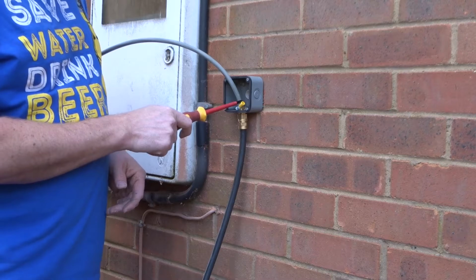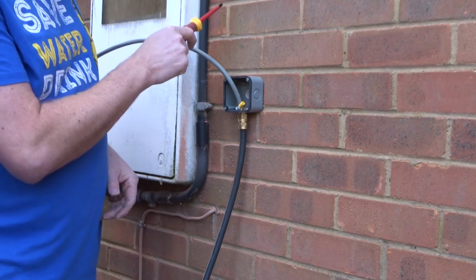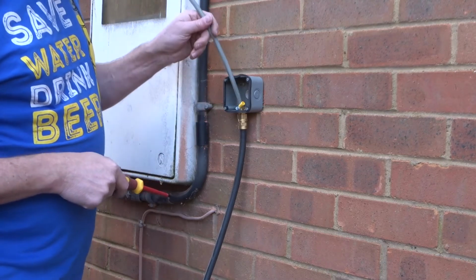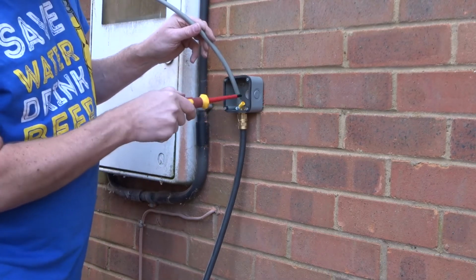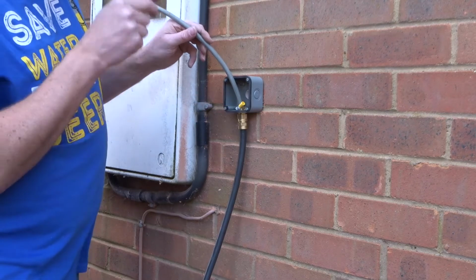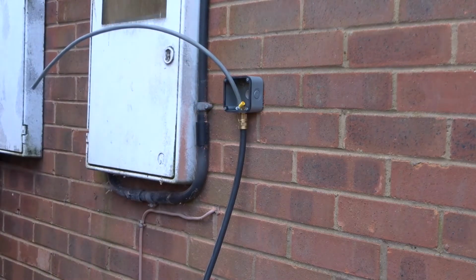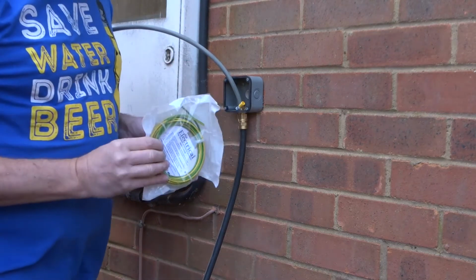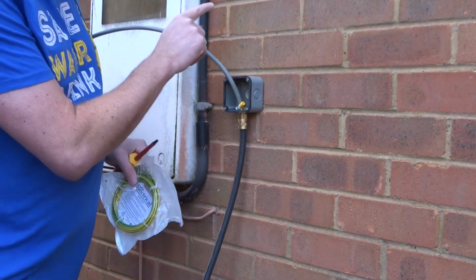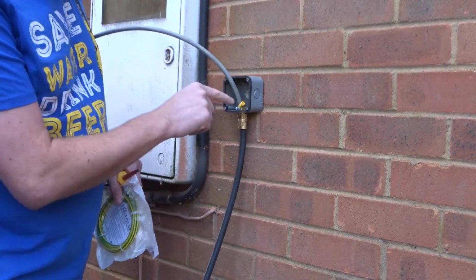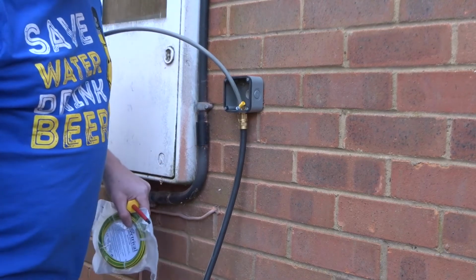This here is for an earthing wire, which will come from the box inside. Because I'm not terminating the wires here, I can't just loop it in, so I'm going to bring a dedicated earthing wire from the main earthing strap in the distribution box to earth this, so that whole cable is then earthed.